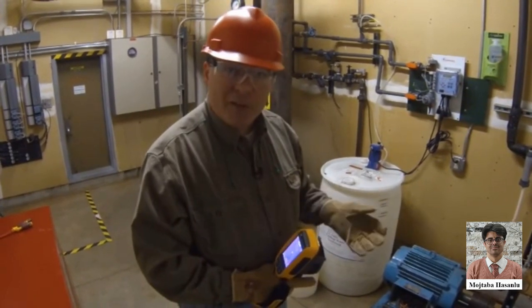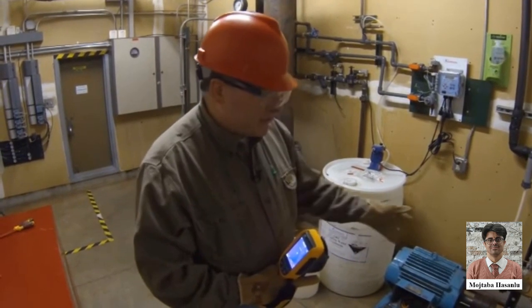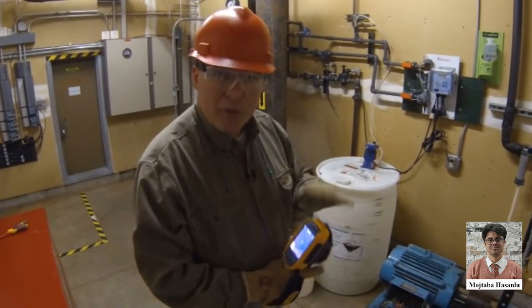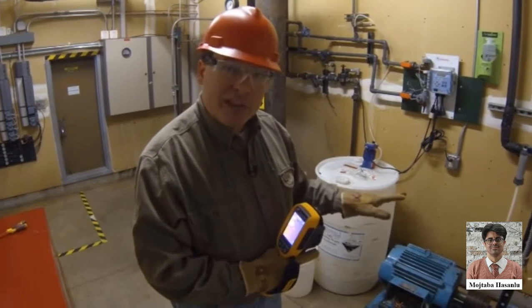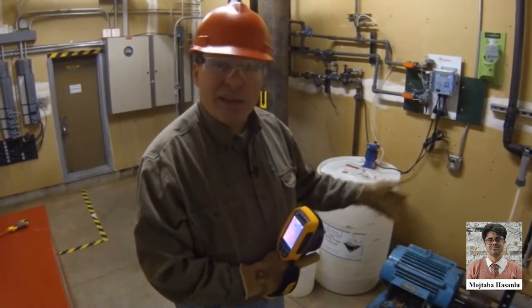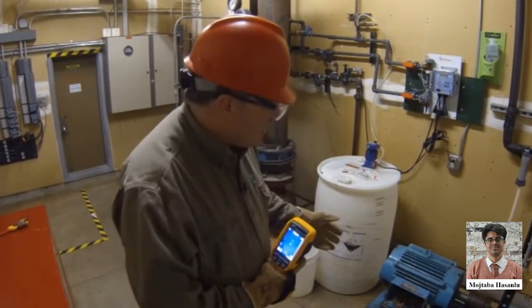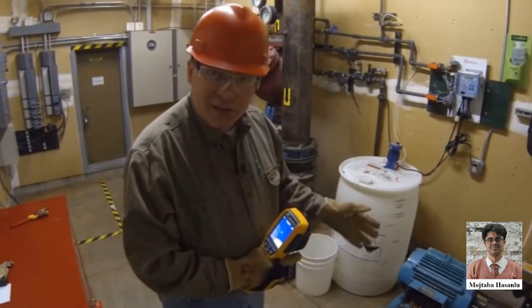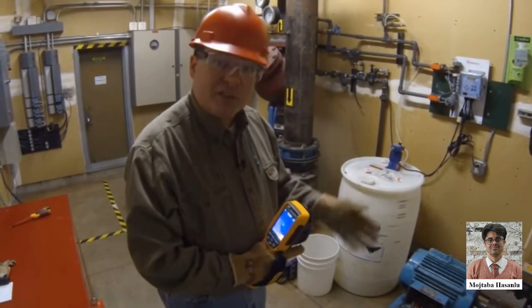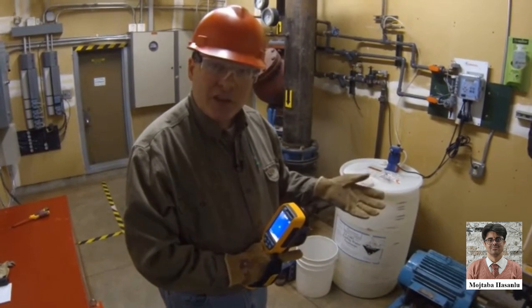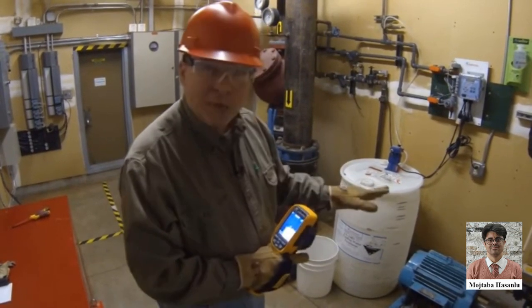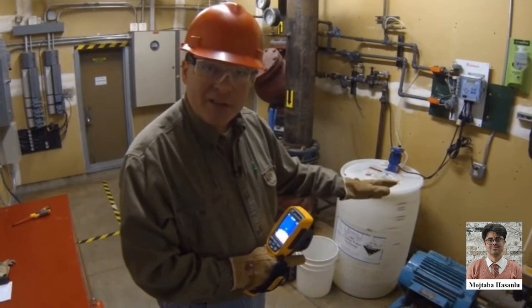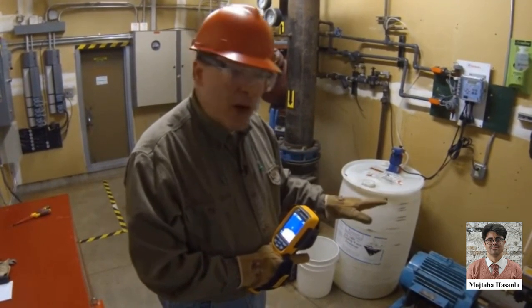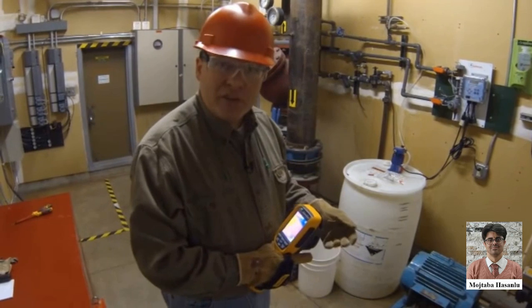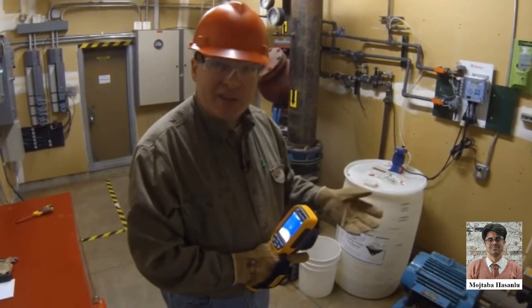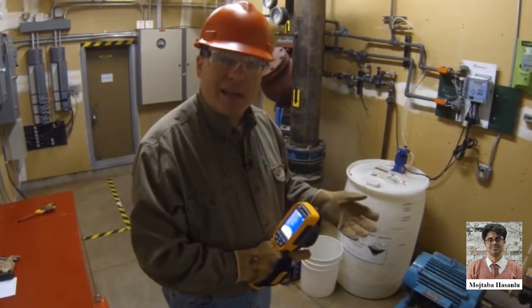Well, you have to be able to diagnose it. So a lot of things, if you're finding a problem with a thermal imager and it looks like it's bearing related or coupling related, you can then use a vibration tester. From an electrical standpoint, if you find a high resistance connection or something looks like it might be overloaded, you can use a clamp meter. If you're finding problems that are localized hotspots, it might be a problem with internal windings, it's a good opportunity to use a power quality meter. It could be, as I said, transients, harmonics, anything like that.